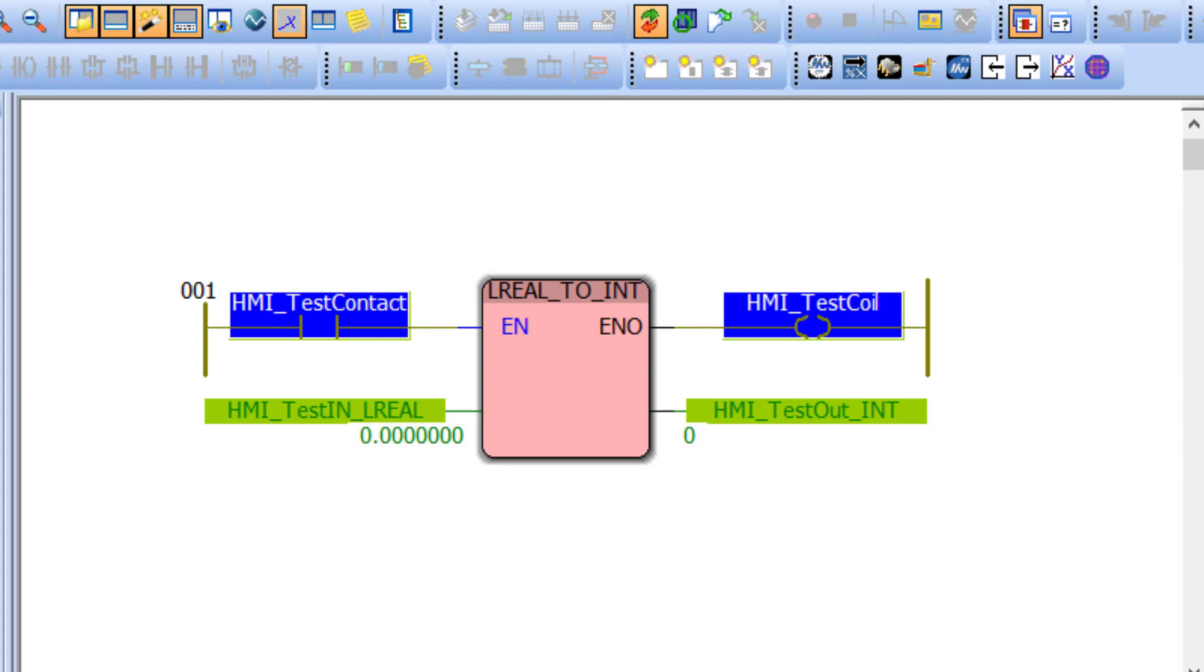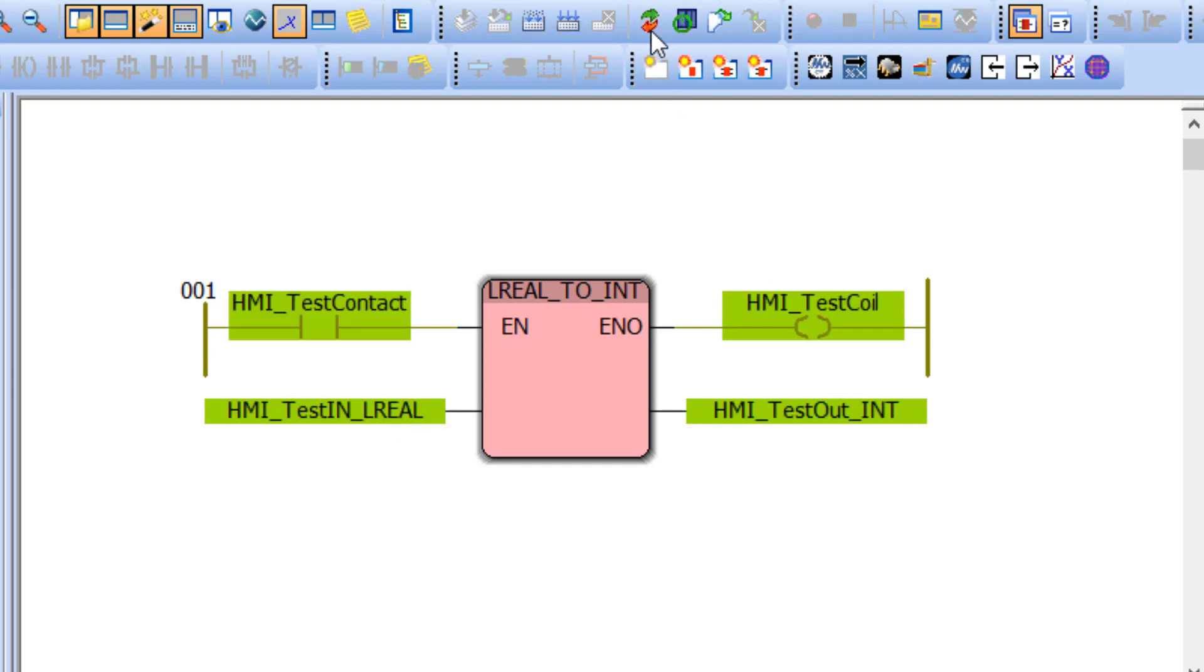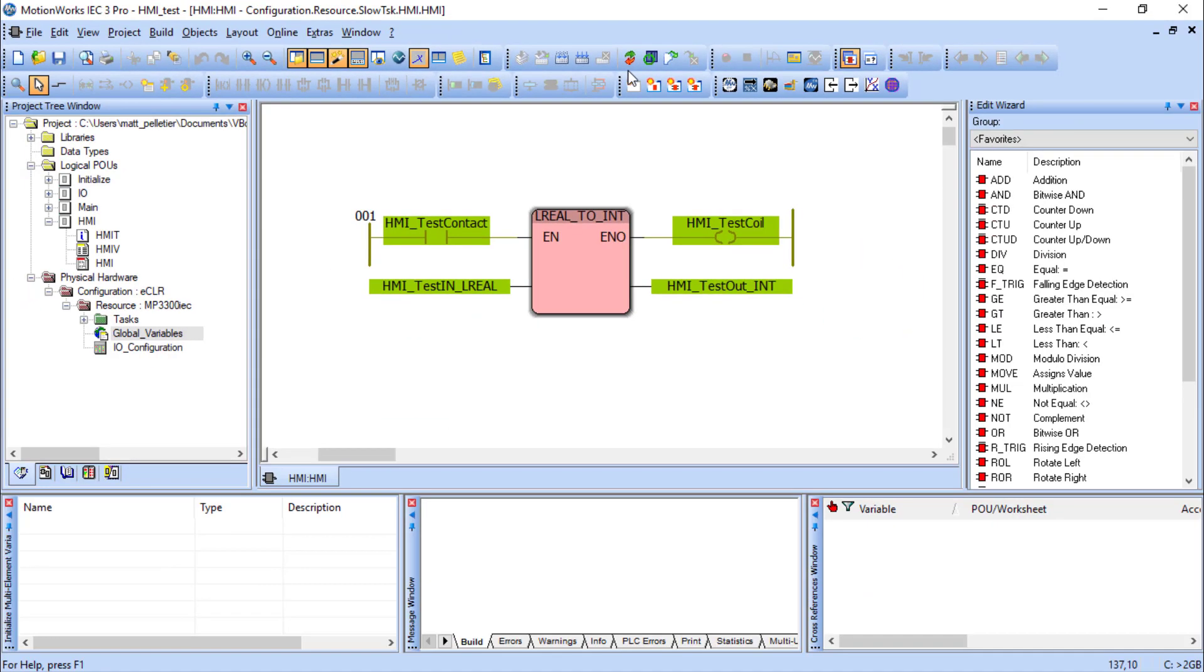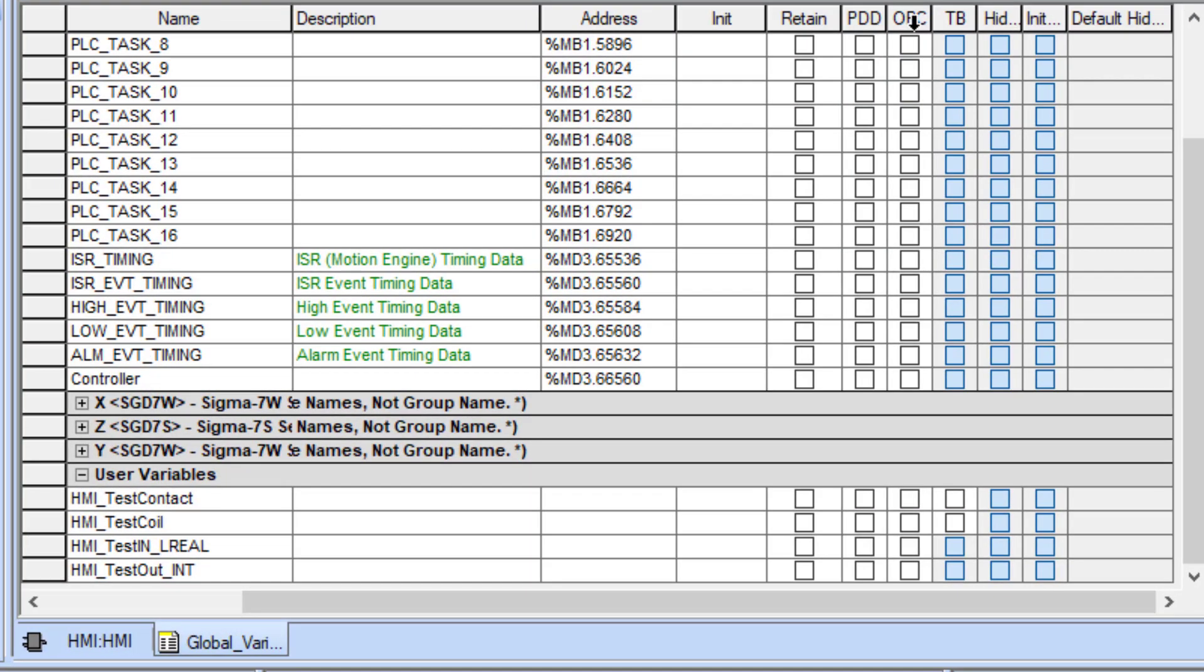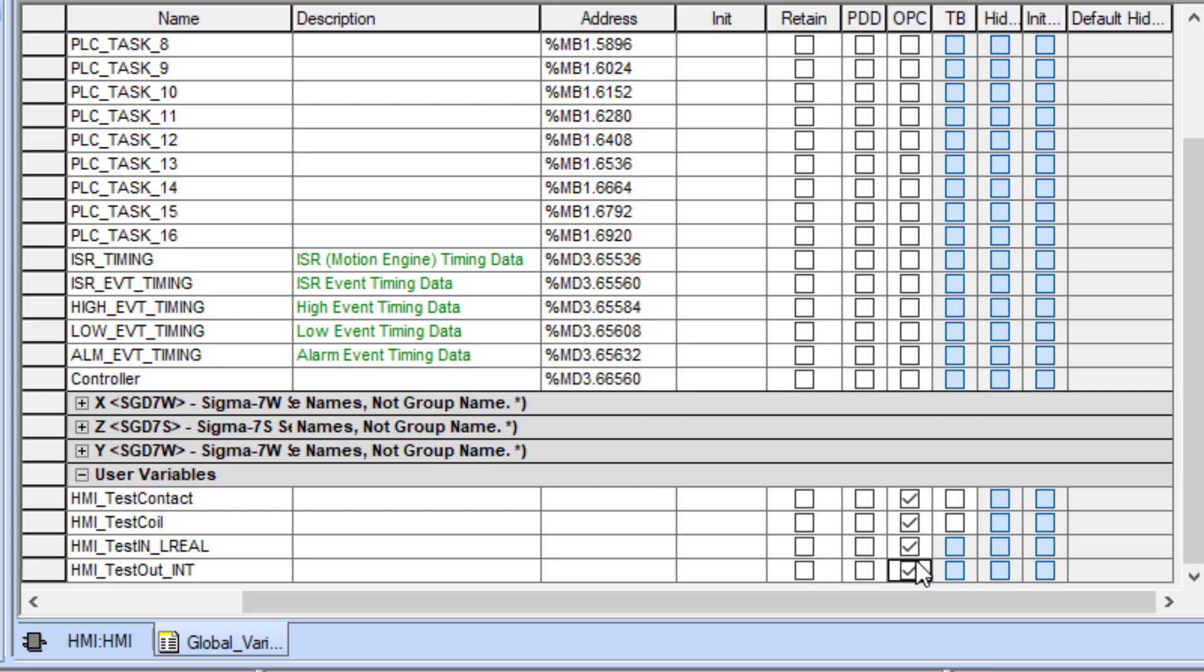The first step to getting these variables into the HMI is to mark the OPC property for each of them. So let's get out of debug mode and look at the global variable list. You can see each of these variables has the property OPC. I'll check that. These marked variables will be accessed by the HMI using the OPC communication protocol. Standard Modbus protocol is also supported by the HMI, but you'll find that OPC is much faster and a lot easier to use.